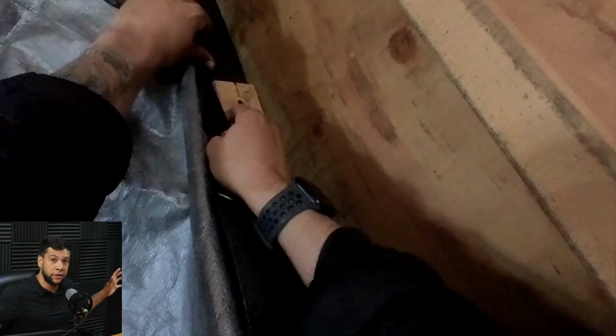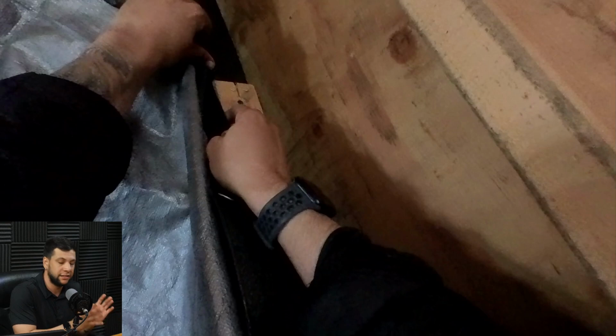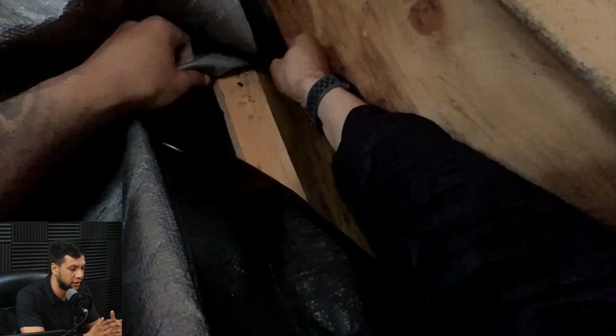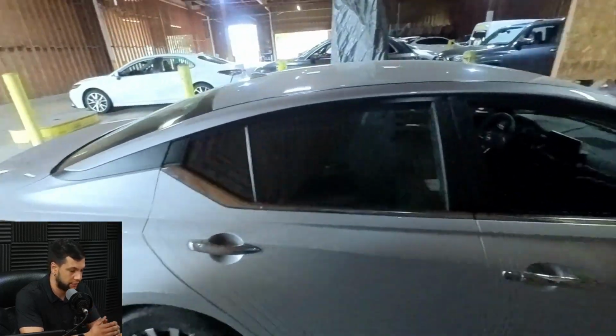Again, this is not the end of the world. If you try to perform the calibration and because of the brightness it doesn't work, the tablet will give you feedback. Sometimes it will tell you that the reason is the brightness. Sometimes you have to figure this out, but I guarantee that if you pay attention and put this in one of your first steps, you will see that maybe you have to change the brightness a little bit, okay? So right here I'm making sure that all the brightness is going to the targets because the weather is dark. So beforehand I'm checking the weather and making sure that I'm gonna have the right environment to do the calibration.